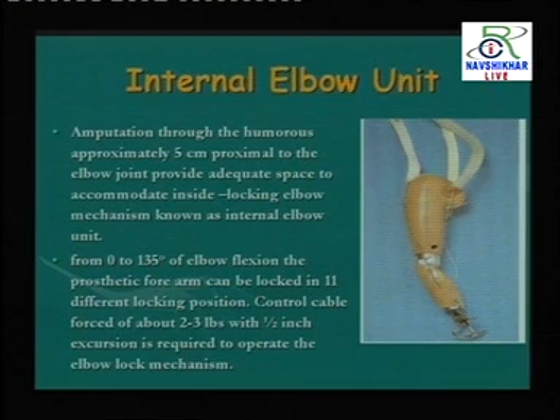If you see the figure, it's very clear that if the amputation level and the stump condition are adequate to give a space of at least 5 cm for the internal elbow joint, then we will go for an internal elbow unit. With this internal elbow unit we can give elbow flexion of 0 to 135 degrees, and the control cable can transmit force up to half-inch excursion, and the amount of force is 2 to 3 pounds. These are the things.